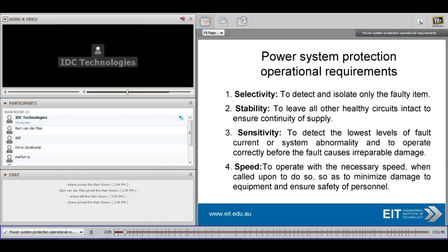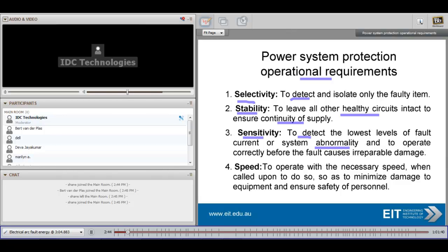The power protection system has four operational requirements. First, selectivity — to detect and isolate only the faulty item. Second, stability — to leave all other healthy circuits intact so that we have continuity of supply. Third, sensitivity — we need to detect the lowest level of fault current or any system abnormality, and it must operate correctly before the fault can cause irreparable damage. And lastly, speed — it must operate with the necessary speed when called upon, which will minimize damage to equipment and ensure safety for personnel.